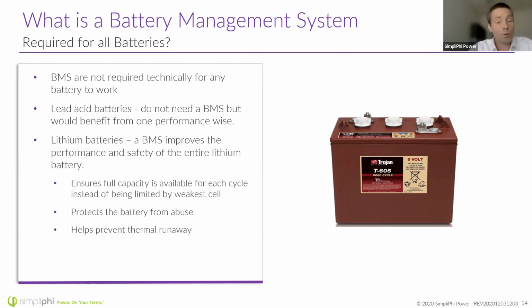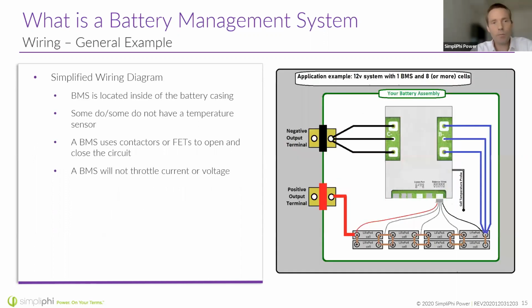It also protects the batteries from abuse. One of the goals of the BMS is to be the last stop as a fail-safe for protecting the battery. So if we put too high of a voltage on our BMS, it will open the circuit and protect that battery from damage. It can also help protect against thermal runaway in the event of a thermal event, maybe the battery was dropped or punctured. The battery can open circuit and prevent more cells from discharging.